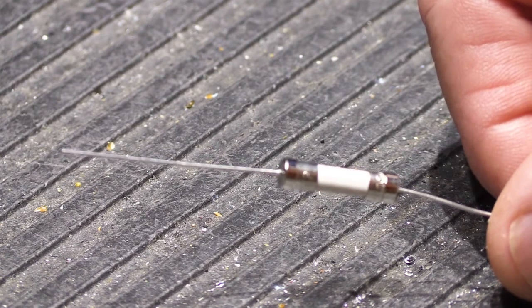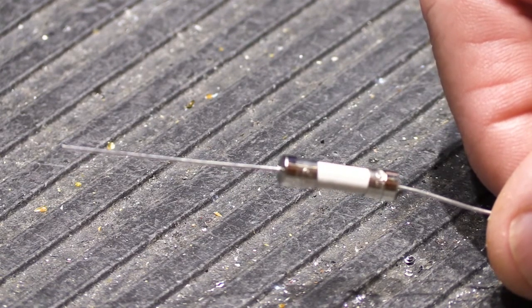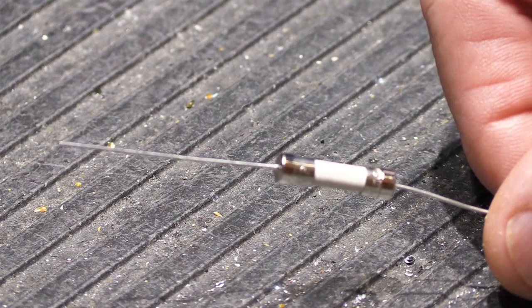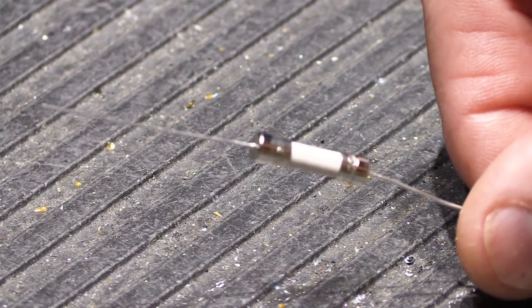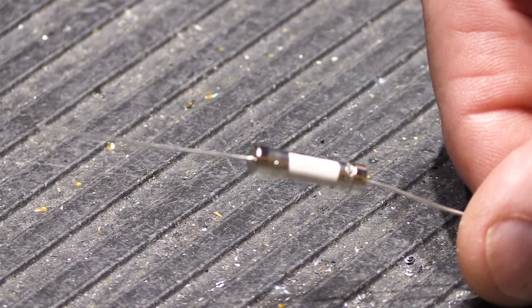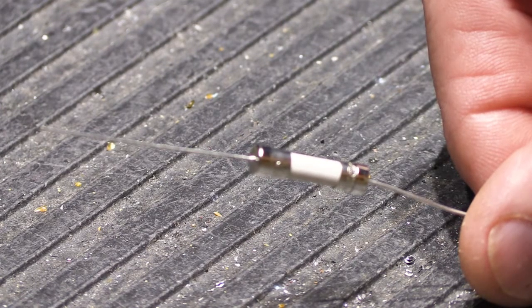Also, this transformer was UL rated with a fast acting fuse, and since we don't want to violate the UL rating, we're going to replace it with exactly the same type of fuse. Any other choice than this would be negligent and a hazard and should not be done.